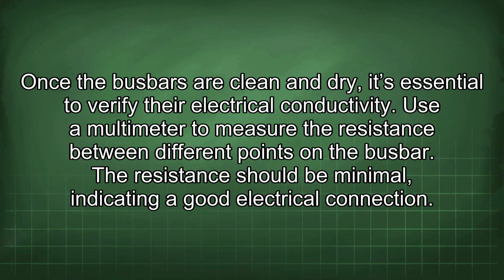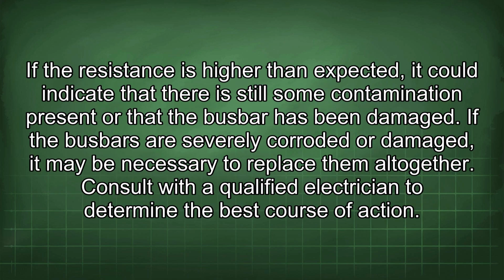Once the busbars are clean and dry, it's essential to verify their electrical conductivity. Use a multimeter to measure the resistance between different points on the busbar. The resistance should be minimal, indicating a good electrical connection. If the resistance is higher than expected, it could indicate that there is still some contamination present or that the busbar has been damaged. If the busbars are severely corroded or damaged, it may be necessary to replace them altogether. Consult with a qualified electrician to determine the best course of action.